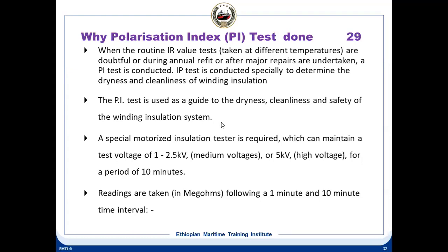So if you get a value less than 2, that means the winding has to be cleaned, dried up, revarnished, and heated up. Again, check the values, and try again till you get higher values. If you don't get higher values after 3-4 attempts, that means the winding has to be rewound.